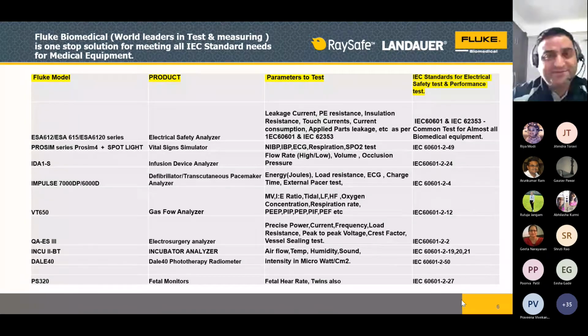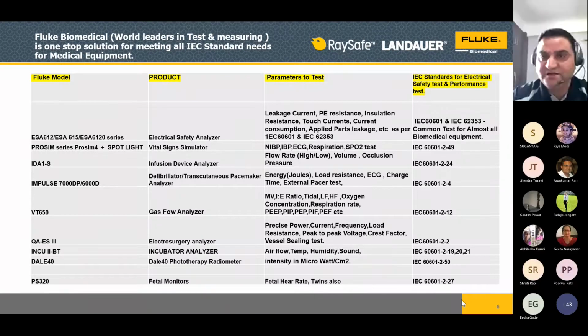Electrical safety means whether your equipment is safe for patient use or not. If your equipment is not safe for patient use, please rectify it, repair it, then again do the testing. Once you ensure that it is fully operational and meeting the standards, only then can you use that particular machine on the patient. After that, once you have ensured that the electrical safety part is fine, secondly it comes to performance parameters. What are the outputs you are generating from the machine? Suppose we are talking about a patient monitor, which is commonly used in all hospitals.